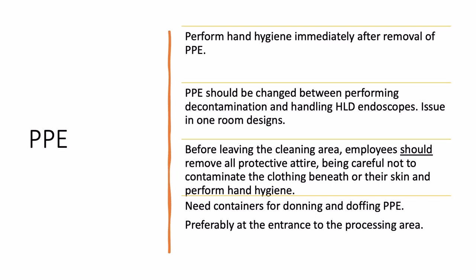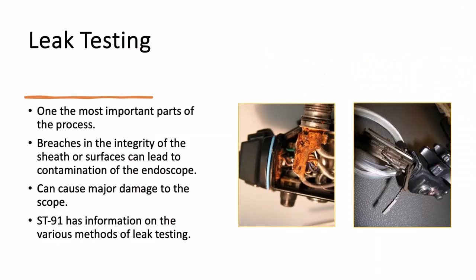Before leaving the cleaning area, employees should remove all their protective attire, being careful not to contaminate the clothing beneath or their skin, and perform hand hygiene. You're going to need a container for donning and doffing PPE, preferably at the entrance to the processing area, so whoever is coming in doesn't have to walk through the area to put on their PPE. Leak testing. This is one of the most important parts of the process because any breach in the integrity of the sheath of the scope or the surface can lead to contamination of the endoscope. This can cause major damage to the scope, like you see here. And ST91 has information on the different methods of leak testing.